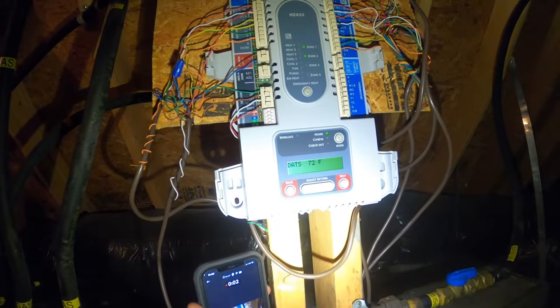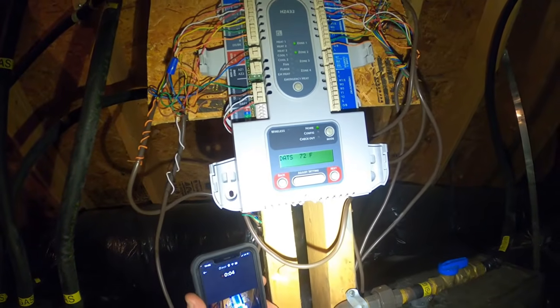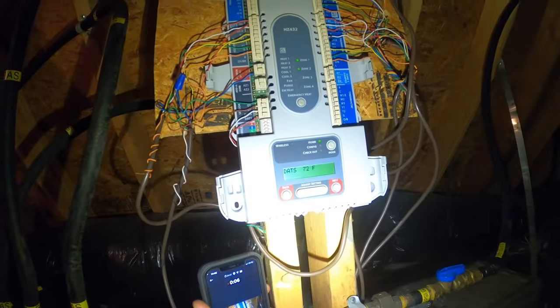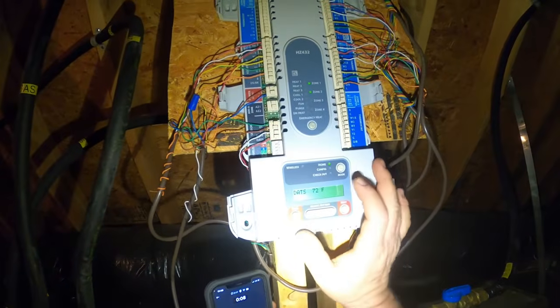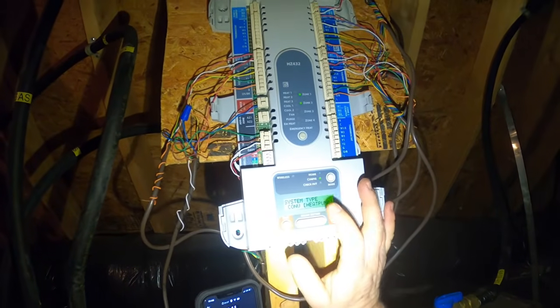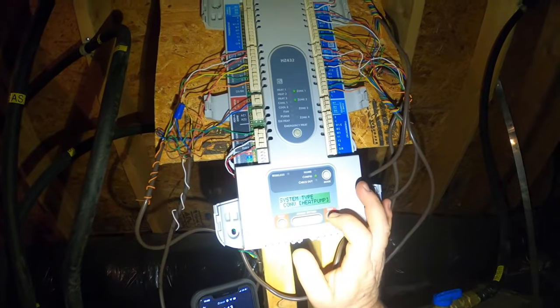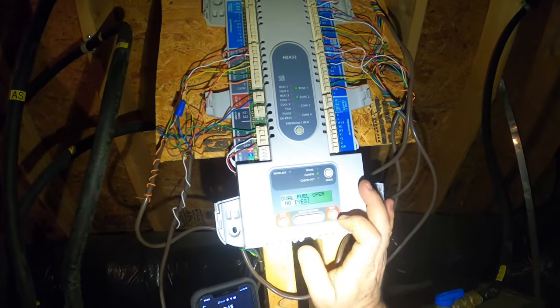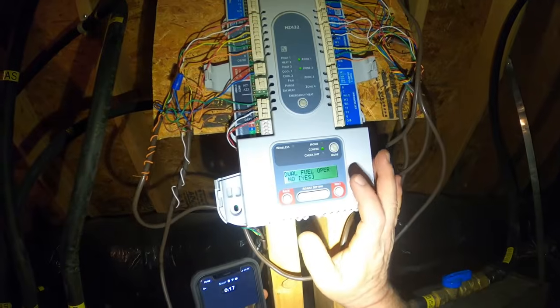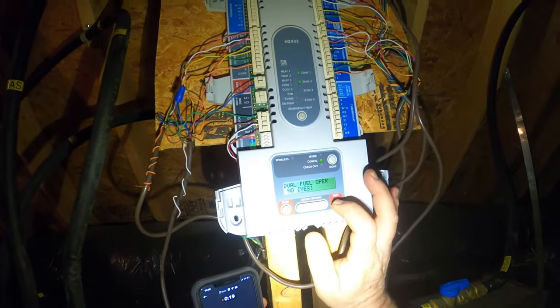Okay guys, we got everything powered up. Still haven't put the thermostats up. I have to set those up, but I do have them wired. I'm going to come over and get this zone board. So we're going to go to configuration, system type. It's going to be a heat pump. Dual fuel operations, yes, because we have a heat pump. Gas backup, so we're going to make sure that's yes.